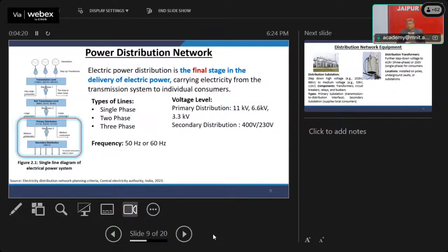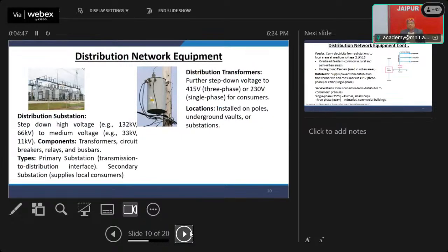We can say 6.6 kV, 11 kV, 3.3 kV, 400 volt, 230. We have single phase, two phase, three phase systems, again 50 and 60 hertz. Electric power distribution is the final stage in the delivery of electrical power. That is the low voltage portion. If you see the diagram, the first two blocks belong to transmission, and the top and bottom two blocks belong to distribution. Next please.